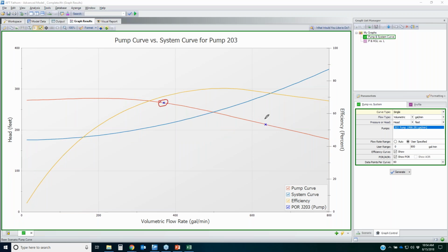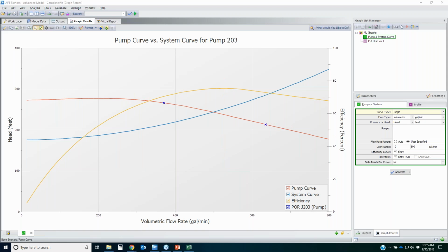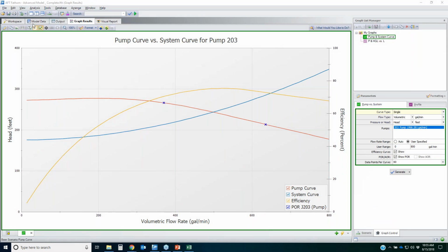Now, what are these two blue dots? Well, that's my preferred operating range. So this is 70% of the BEP. This is 120% of the BEP. Where's my best efficiency point? Well, the yellow curve is my efficiency curve, so the BEP is going to be right about here. Okay, so if I drew a vertical line, that's my best efficiency point. Here's my operating point. It's very close to that BEP, so it's really good. I want to make sure that this operating point does not go this direction or this direction past these X's right here, okay? So in this original design, everything is working exactly the way it should.